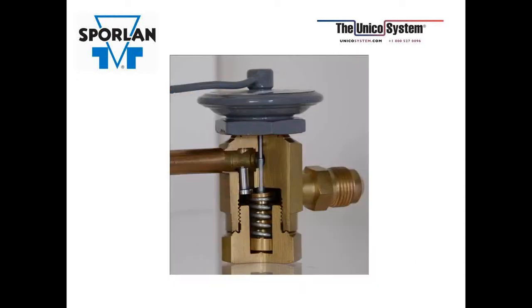Here's a cutaway view of the internal parts for a CBBI valve that is non-adjustable. So the thermostatic element is made up of the lock ring. It's made up of the casing, the diaphragm, the bulb, and the capillary tube that attaches to it. So all that is the thermostatic element.